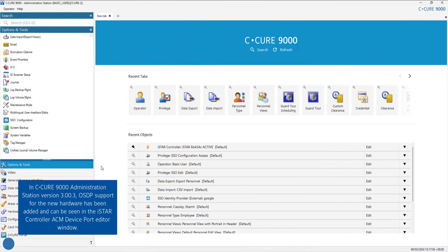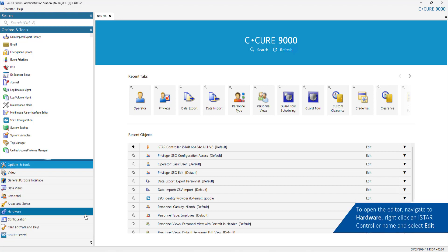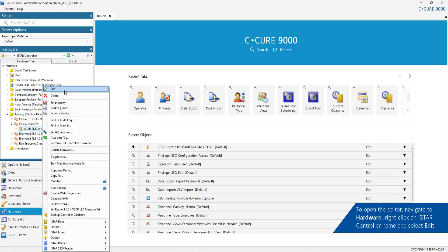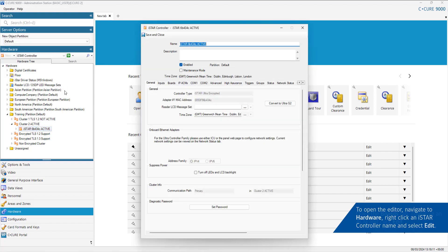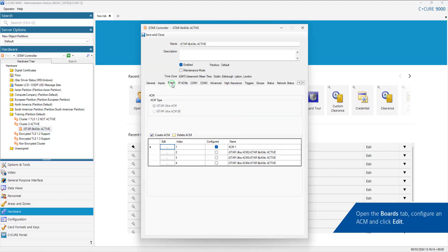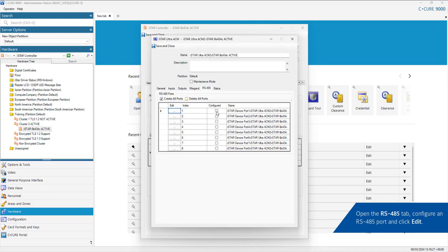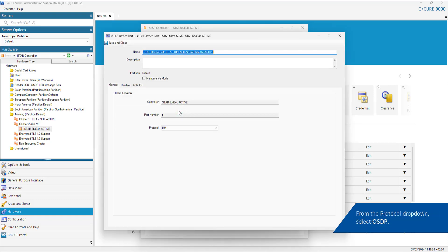In C-CURE 9000 admin station version 3.00.3, OSDP support for the new hardware has been added and can be seen in the iStar controller ACM device port editor window. To open the editor, navigate to Hardware, right-click on an iStar controller name and select Edit. Open the Boards tab, configure an ACM and click Edit. Open the RS485 tab, configure an RS485 port and click Edit. From the Protocol drop-down, select OSDP.